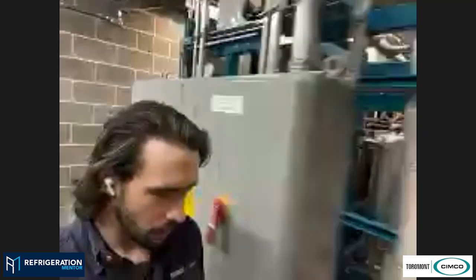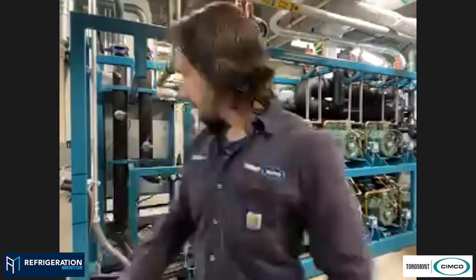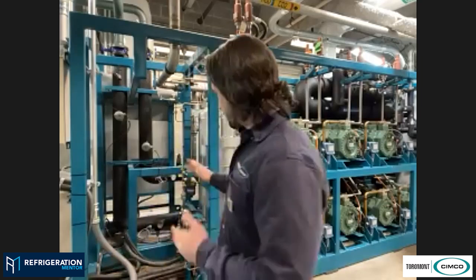So when we're running transcritical or during warmer high load times, the ability to harness as much heat as we can at that exchanger really helps the system a lot. We're taking all that load off our gas cooler, which has to extract heat under high ambient conditions outside. Here in Reading, Pennsylvania, we get very humid, very warm days, 95 degrees with high humidity. It can almost be like Florida here in the middle of summer sometimes. So having that, in my opinion, is a big win.